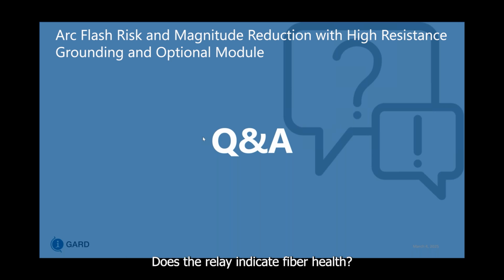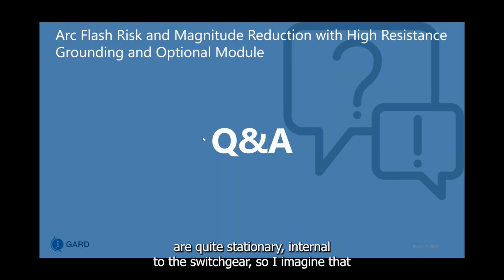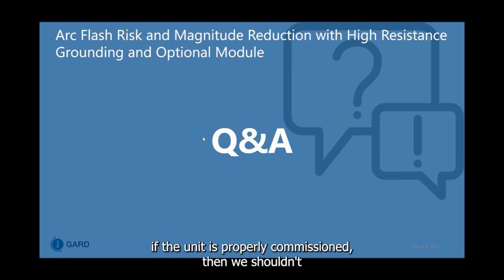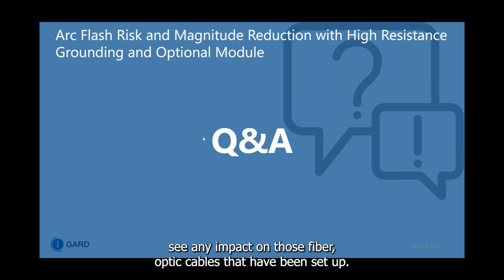Does the relay indicate fiber health? I don't believe it does, but these fibers are quite stationary internal to the switchgear. So I'd imagine that if the unit is properly commissioned, then we shouldn't see any impact on those fiber optic cables that have been set up.